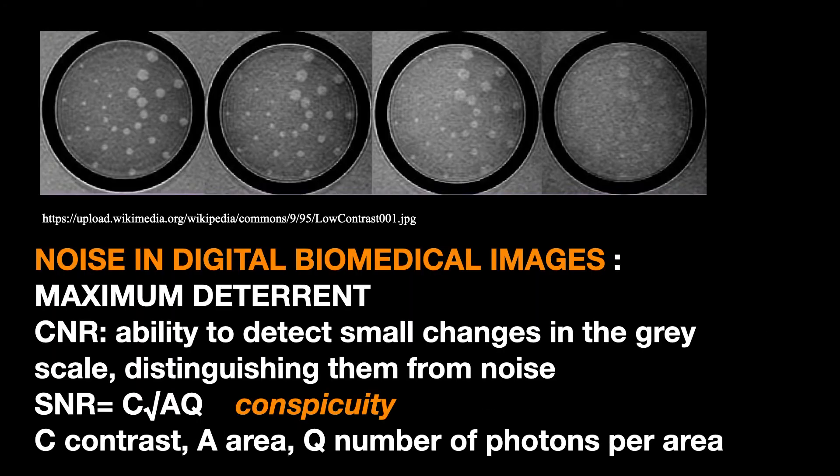I said a very high contrast resolution is needed in mammography, but I also have to point out the importance of noise, which is the maximum deterrent of quality in every biomedical digital image. Rather than contrast, we should talk about contrast-to-noise ratio, CNR. It expresses the ability to detect very small changes in the grayscale, distinguishing them from noise.